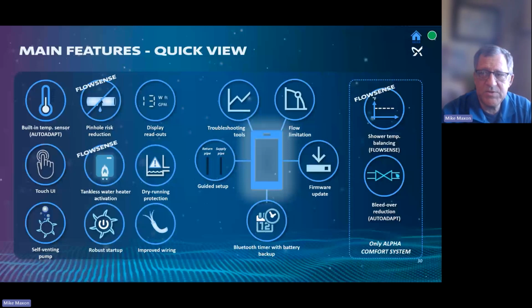What we're calling flow sense, being able to know what our flow is, gives us the capability of making sure we fire up tankless boilers and preventing pinholes within pipes. And built-in temperature sensor. The Alpha Comfort has the great feature of being able to make sure that we don't have bleed over across our comfort valve, as well as the flow sense gives us the capability of making sure that we don't offset a house hot water system on the pressure of the hot water side.